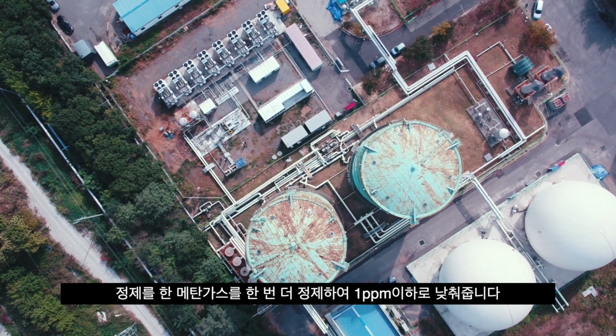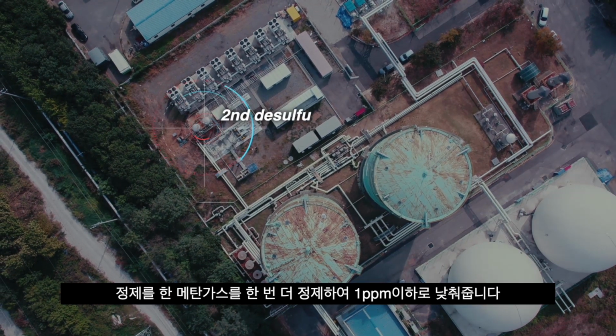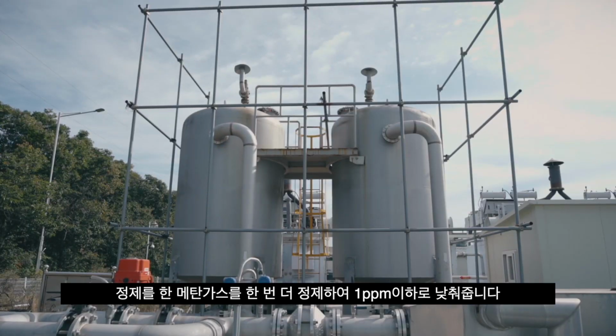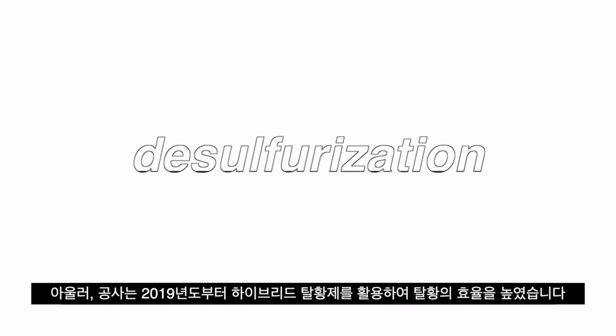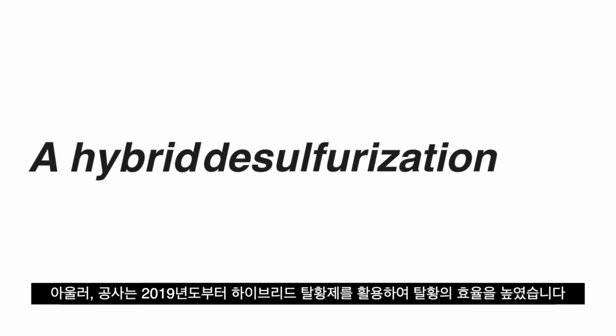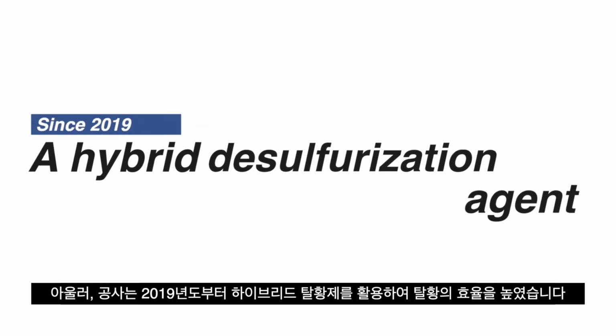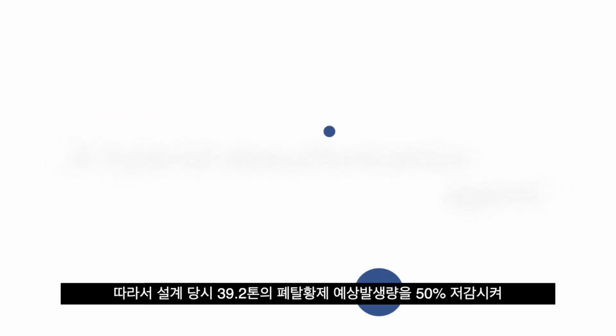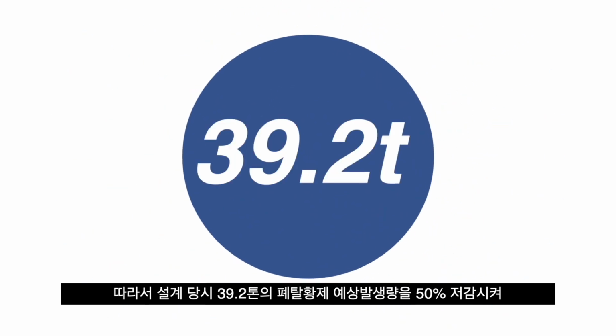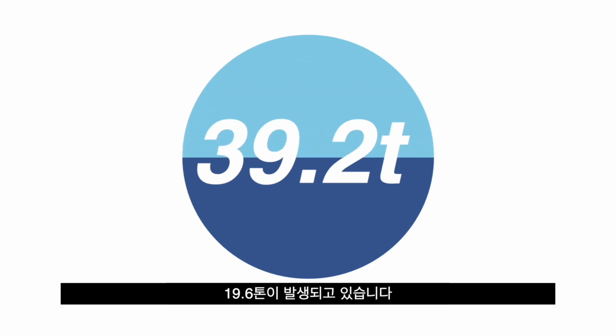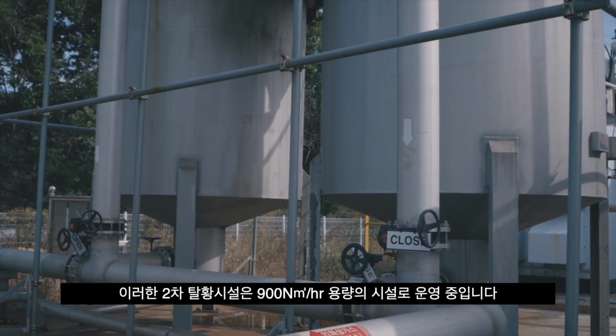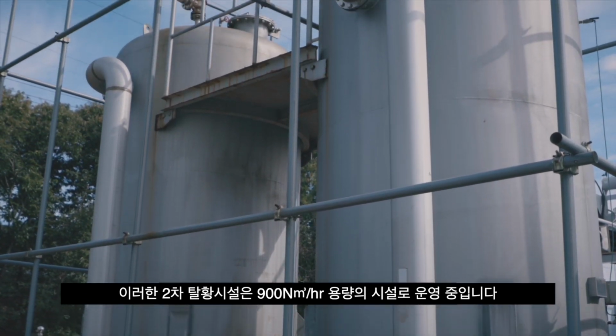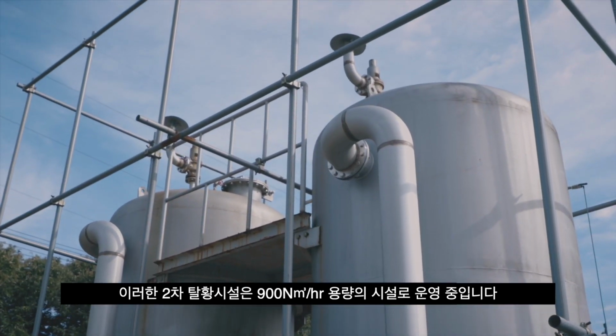The methane gas purified once is purified once more and lowered to less than 1 parts per million. In addition, SLC has increased the efficiency of desulfurization by using a hybrid desulfurization agent since 2019. Therefore, the estimated generation of 39.2 tons of waste desulfurization agent at the time of design was reduced by 50%, resulting in 19.6 tons. These secondary desulfurization facilities are operated with a 900 normal cubic meter per hour capacity.